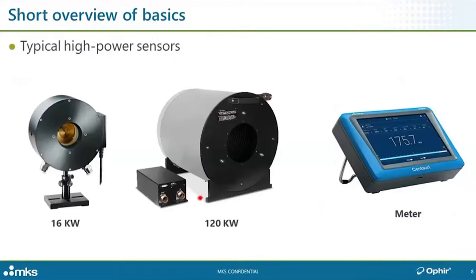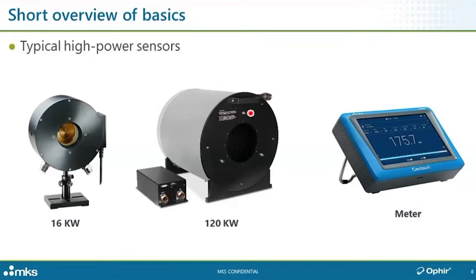Here you see a few examples of such sensors with water connectors — these sensors are generally water cooled. You can see the reflective cone in the aperture. This sensor is designed for up to 16 kilowatts. When it comes to showing actual examples of real devices, I'll be using Ophir devices since those are the ones I can talk about. Here's another sensor designed for measuring up to 120 kilowatts — that's not a mistake. It looks big; it's actually a desktop device, 50 centimeters by 50 centimeters.